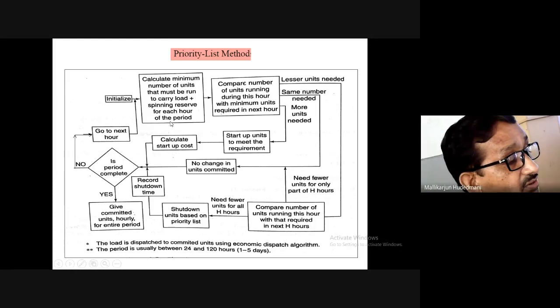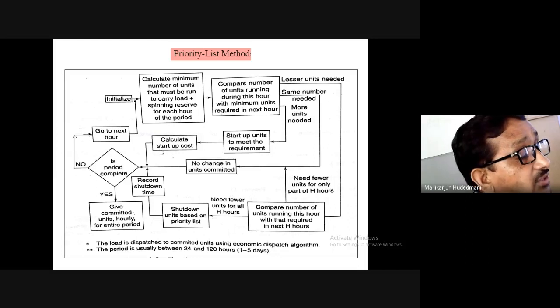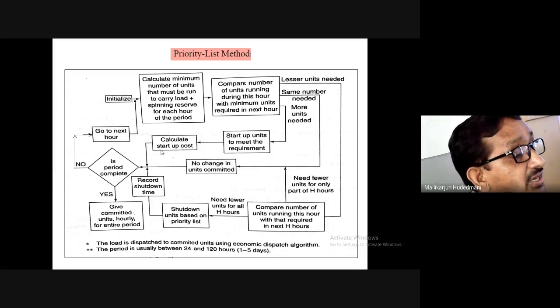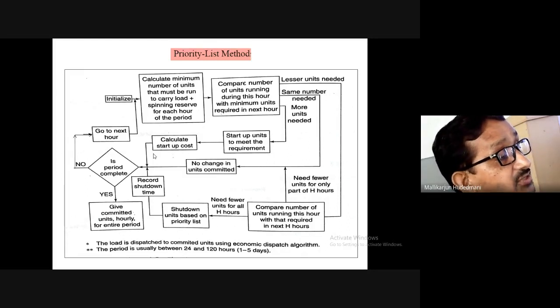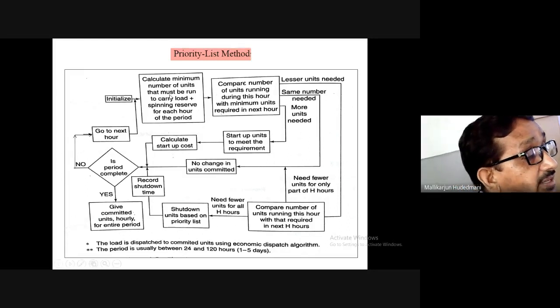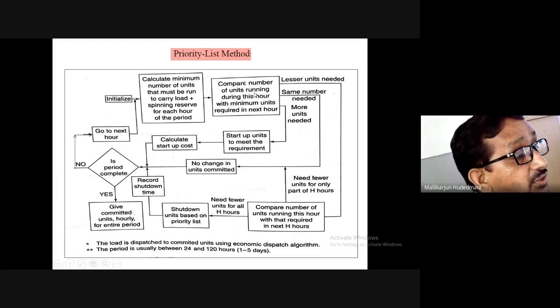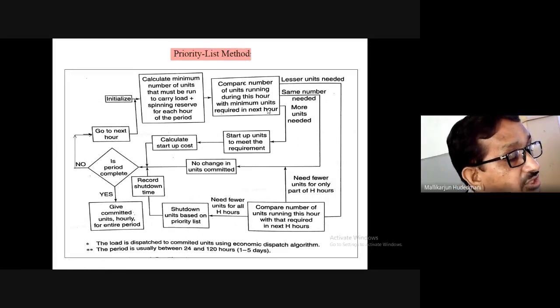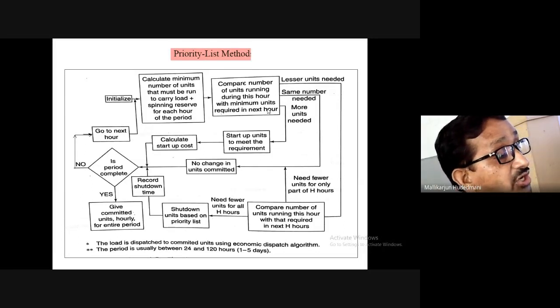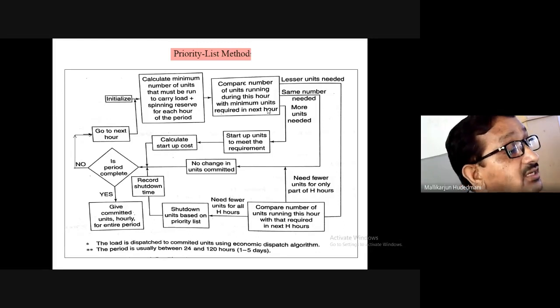Once you decide how many machines you require, what the load is, and what the spinning reserve is, then hour to hour, as you observe the station, the same status may not remain in the next hour. Check it. Compare the number of units running during this hour with the minimum units required for the next hour. I should keep checking the current 6 generators which are running for my 60 minutes of duration. For the next 60 minutes, do I really require all these 6, or do I need to reduce or increase the number of generators? A decision has to be taken every hour.